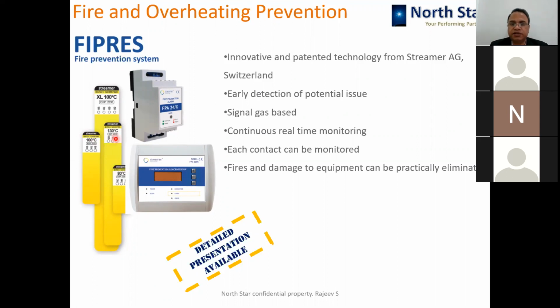When the activation temperature of this sticker is reached, the gas gets burst, which is sensed by this fire protection alarm, and you get an alarm which can be transmitted to your system through this controller box on your mobile as well as on your SCADA or wherever you want to use it, so that you can prevent fire by identifying loose contacts much earlier than the actual event of failure. So it's a very wonderful solution which can help in containing fire incidences and damage to property.